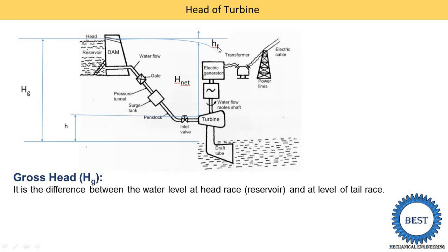The second point is the friction head, Hf — H means head and F means friction. When water is transferred from the reservoir to the tail race through the penstock, friction takes place between the water and the surface of the penstock. This is known as the friction head. Due to this friction, water loses a certain amount of energy, so this friction loss is subtracted from the gross head.